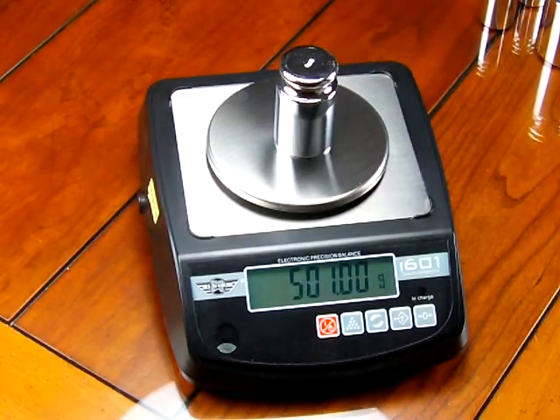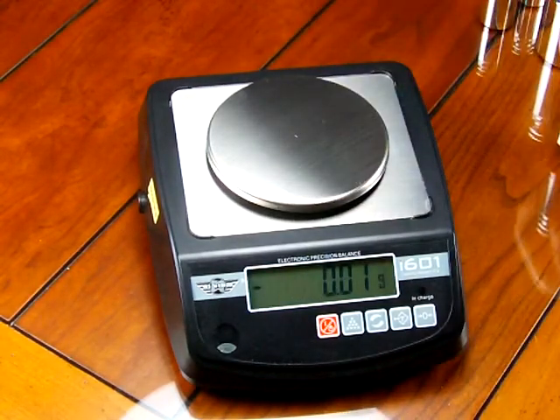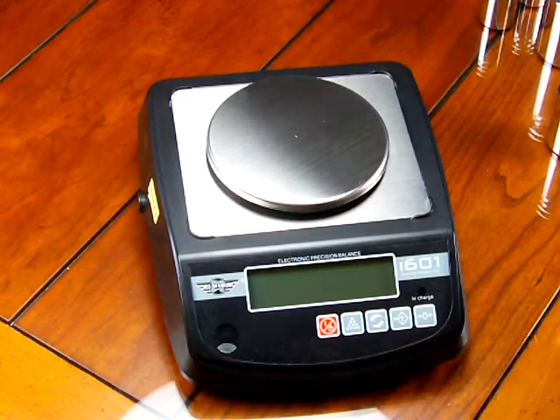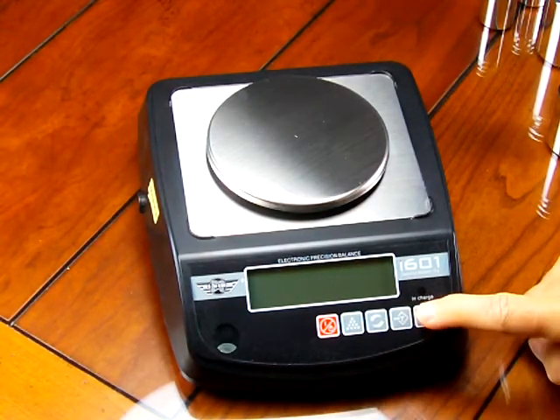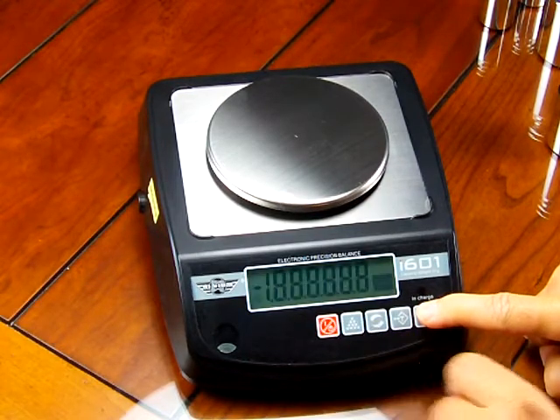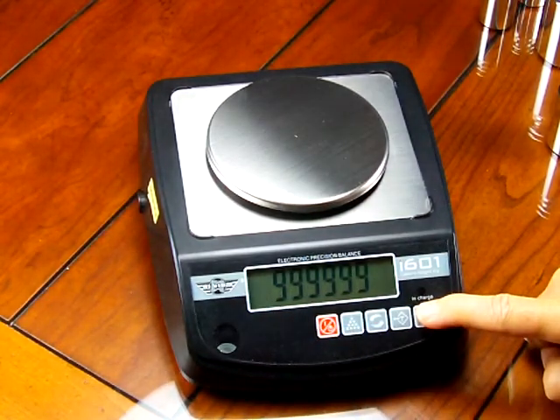So we are going to walk through the calibration. What this means is you need to have the scale off. You want to press the zero key down. You want to turn the scale on. This is the power up test.